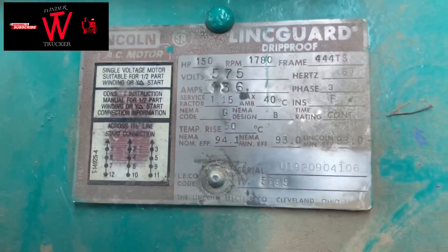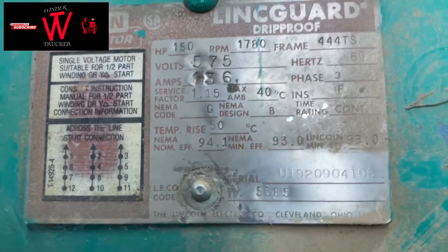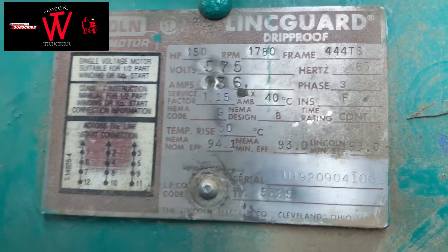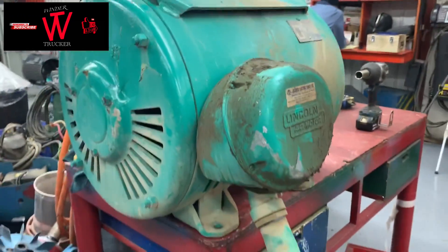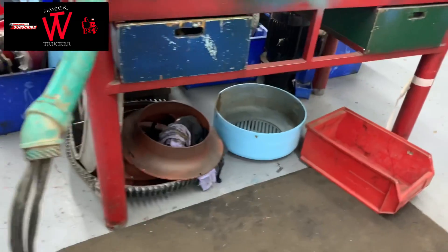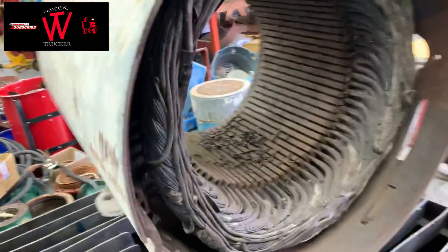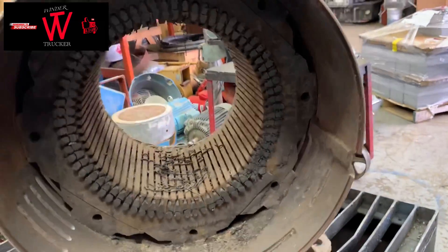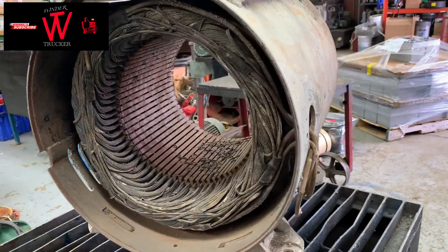Hello winders, so I have here a 150 horsepower Lincoln motor. It was 12 leads but it's already rewound in six leads. I opened the motor and found out it's burned, so the customer wants to rebuild and rewind it. It just came off from the burn oven. Now I'm going to show you how to trace the connection and take the data of this motor before rewinding.